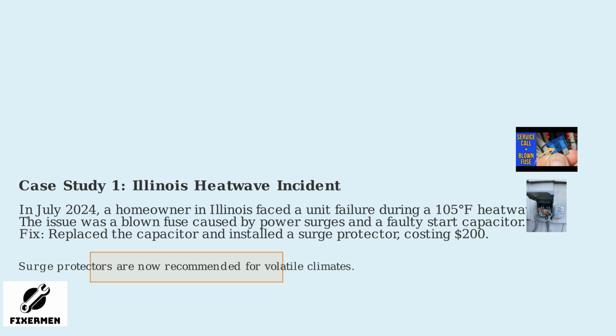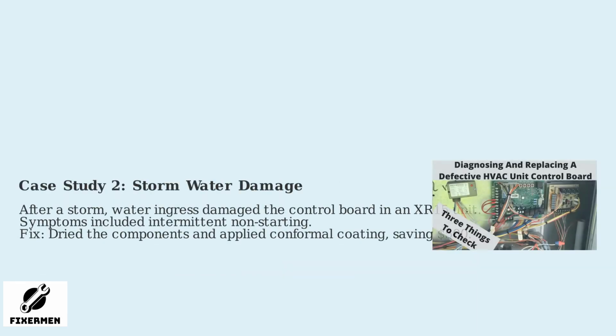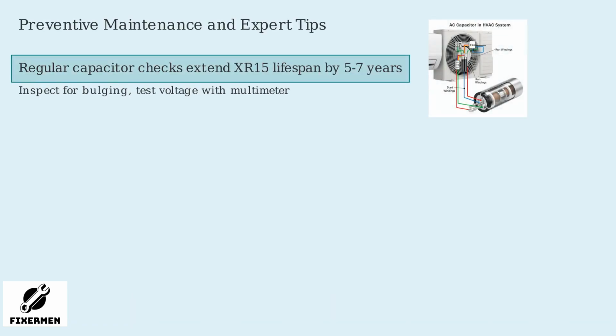costing around $200. Another case involved water damage to the control board after a storm, leading to intermittent non-starting. The resolution was drying the components and applying a protective conformal coating, saving $500 compared to full replacement. This highlights the importance of storm-resistant upgrades. These real-world examples demonstrate how electrical surges and environmental factors can cause startup issues and how targeted fixes can resolve them effectively. Experts recommend regular capacitor checks to extend the XR15's lifespan by 5 to 7 years.